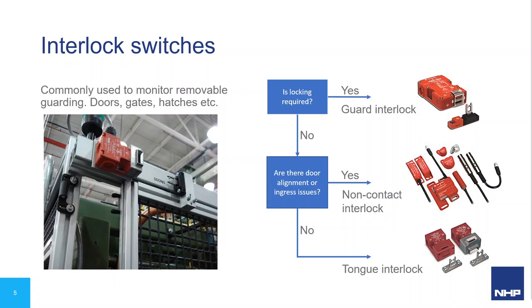There are a few ways to select the right interlock device. First: is locking required? Does the guard need to be physically locked closed? For example, if the guard were opened while the machine was running and the hazard doesn't stop immediately, you'd look at guard interlocking switches. Otherwise, if locking isn't required, are there alignment or ingress issues? A non-contact interlock switch may be most suitable as these are fully sealed and ideal for dusty or clean-in-place applications. Finally, tongue interlocks.